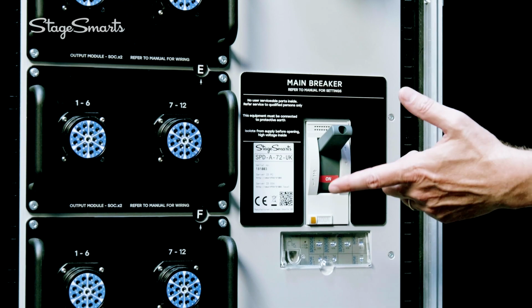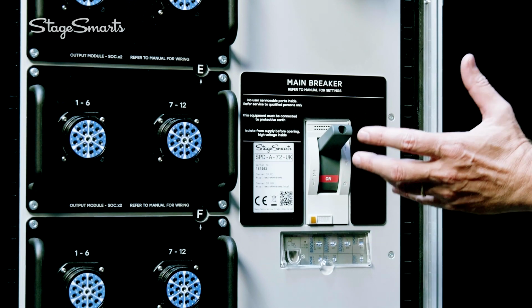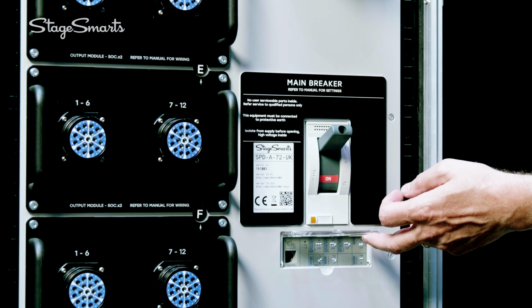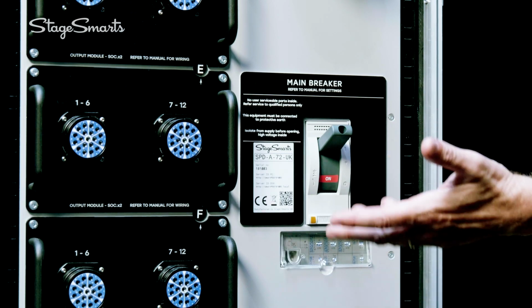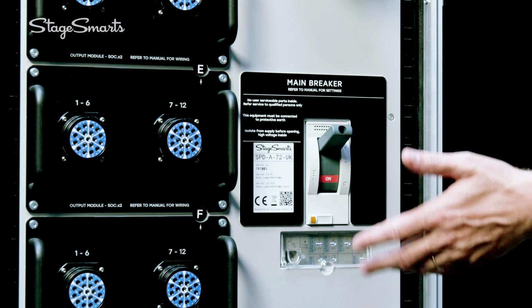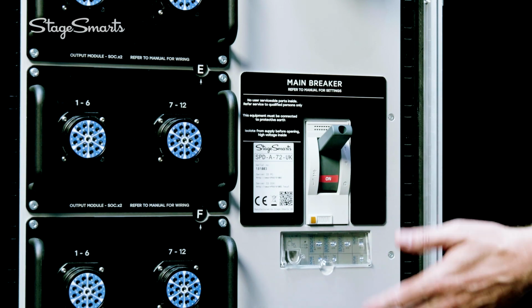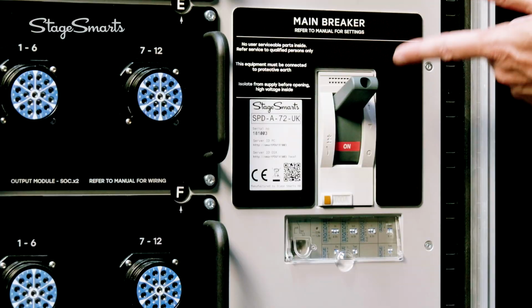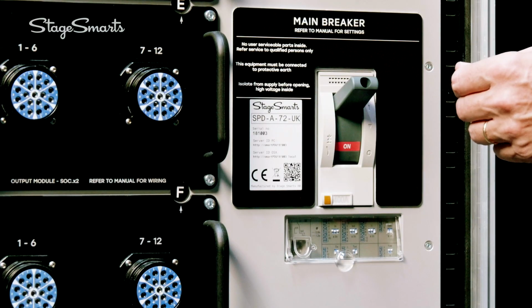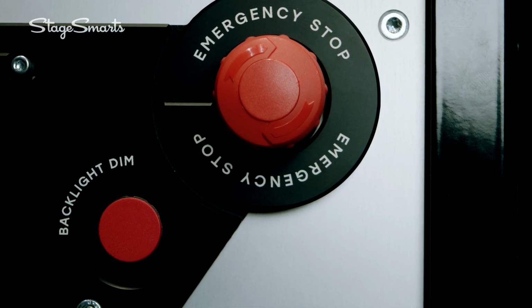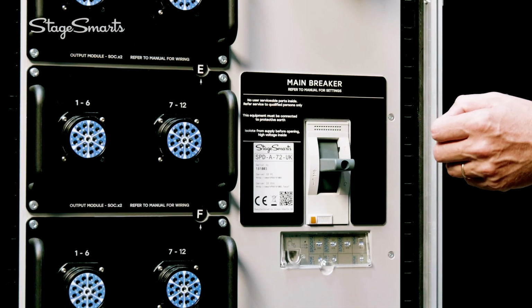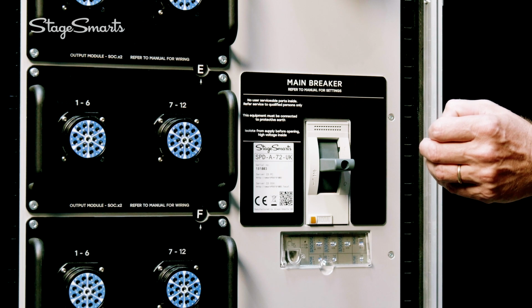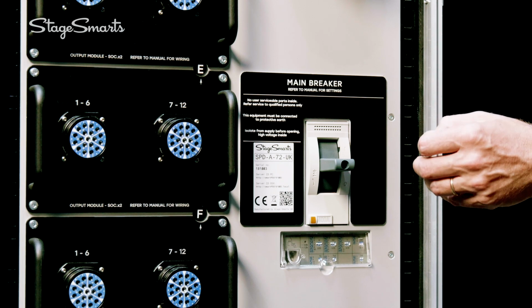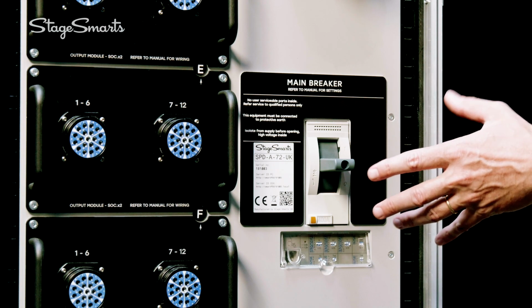Next, we have the main breaker. The main breaker we use is a quite sophisticated one with adjustable settings. So if you want to fine-tune the breaker to the capacity of your power supply, transformer, generator, whatever, the cable gauges, etc., you can do that, or just leave it as it is. The main breaker, of course, trips if there's a serious overload, but it's also energized by the emergency stop and our unique loss of neutral protection. As most people know, if you lose the neutral, you can potentially have 2/3 of your connected loads experiencing overvoltage, which usually results in very, very costly repairs.